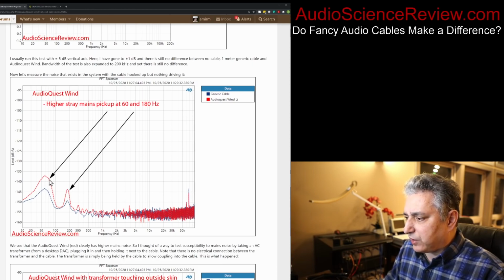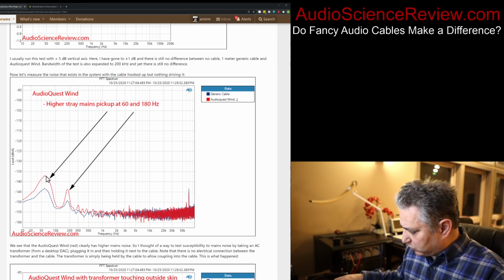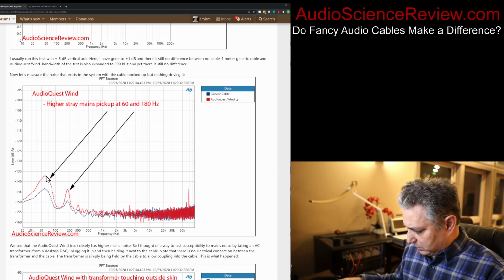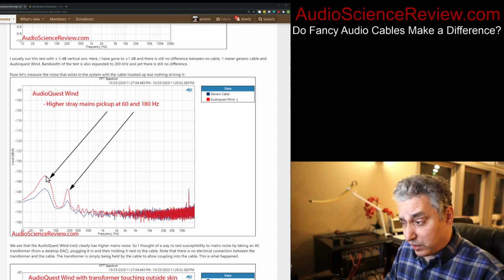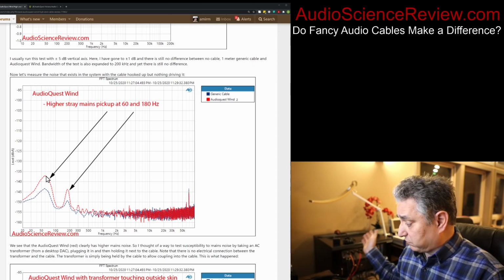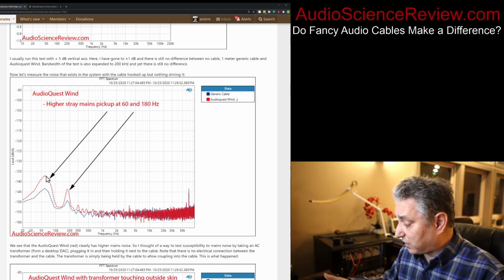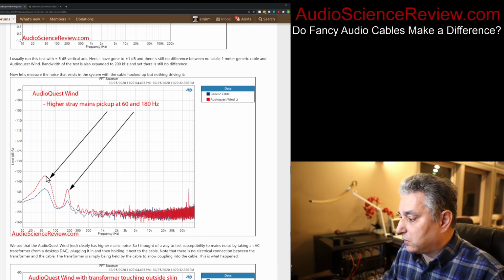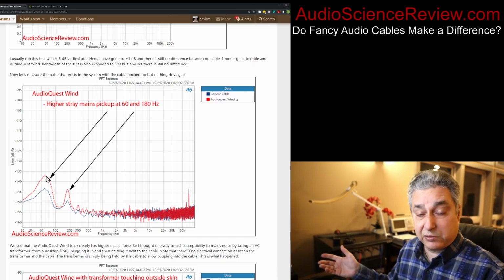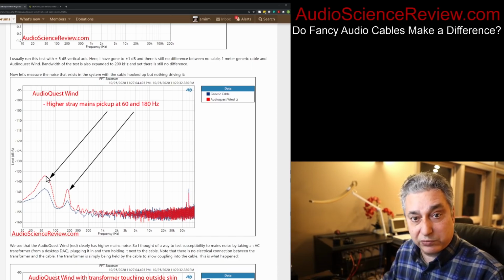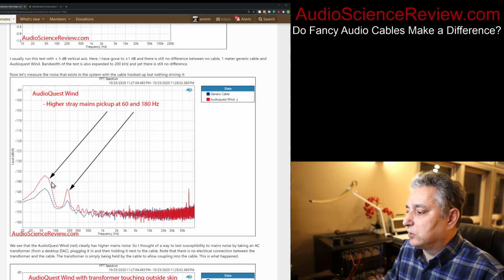It could be an odd harmonic of that 60 hertz. I wanted to figure out the source, and as I was testing, I noticed that if I moved the cable around, the measurement changed. So I thought it might be picking up noise from other equipment in the room — there are a lot of sources of interference, and these cables are supposed to be shielded, but there's no such thing as 100% shielding.